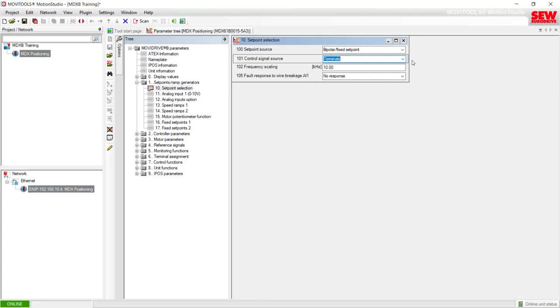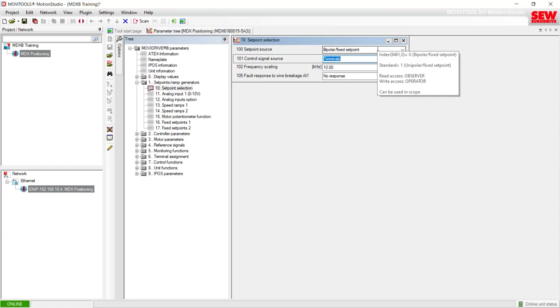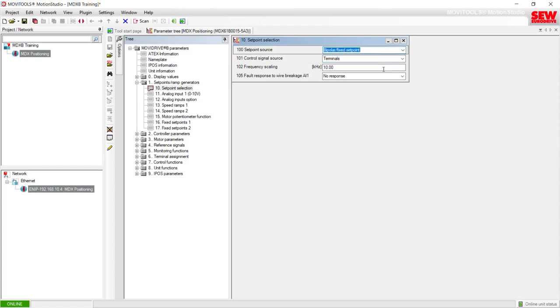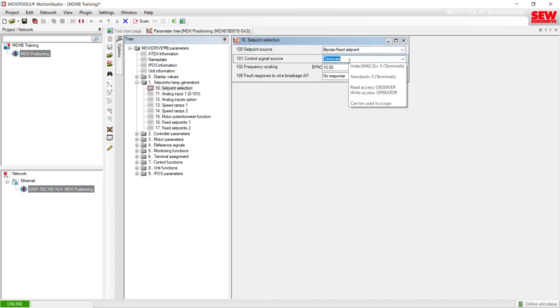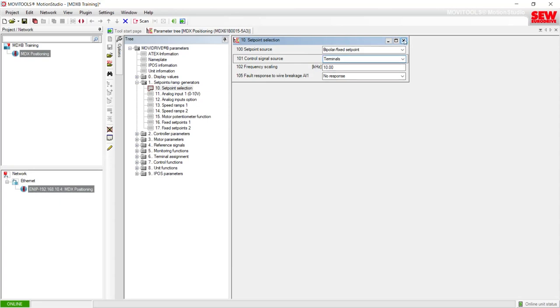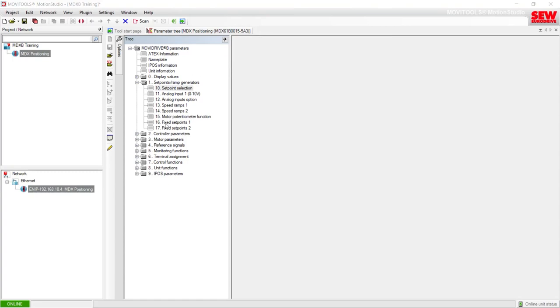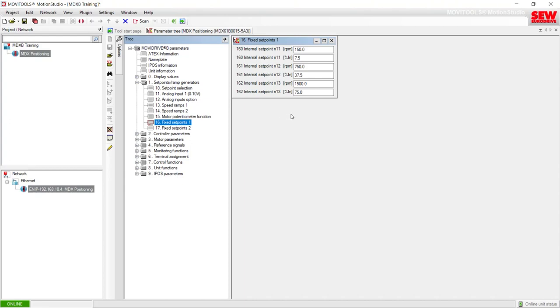Currently, because the IPOS program loaded is Table Positioning over the terminals, it is getting its speed set point from the IPOS program. But if there were no IPOS program loaded, the speed set point in this configuration would be from a bipolar analog input or a fixed set point, controlled via the terminals. To see the speed set points in the basic configuration, I can close item 10 and come down to Fixed Set Points, item 16.